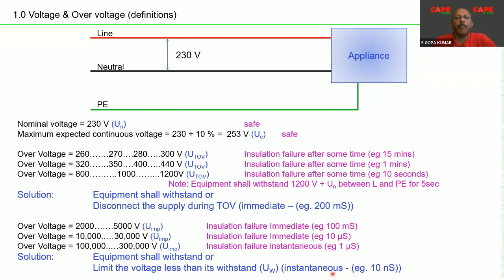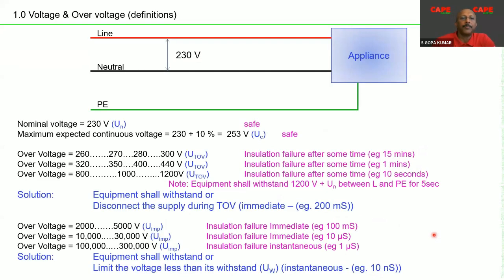Don't make it more than a certain level. So for example, instantaneously, within a short time, in nanoseconds, you limit the voltage. As a result, once you are limiting the voltage, your equipment is safe. So these parameters you should always keep in mind. Now, what equipment shall withstand is an important subject.